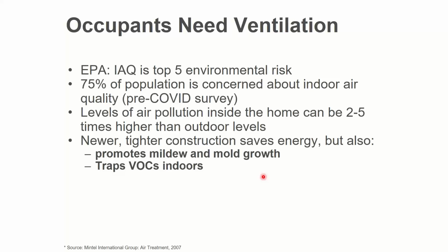I don't care if it's going out a crack, out the front door, out an exhaust system, but if air's coming in, air is definitely leaving. Because if it didn't, the building would blow up like a balloon and explode, right? So if air's coming in, air is definitely going out, and I want air to go out. And that's one way I'm going to get the germs out: bring new fresh air in that hopefully has fewer germs and push the inside germs out.